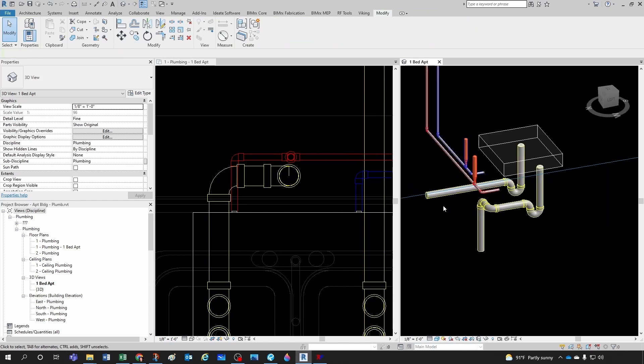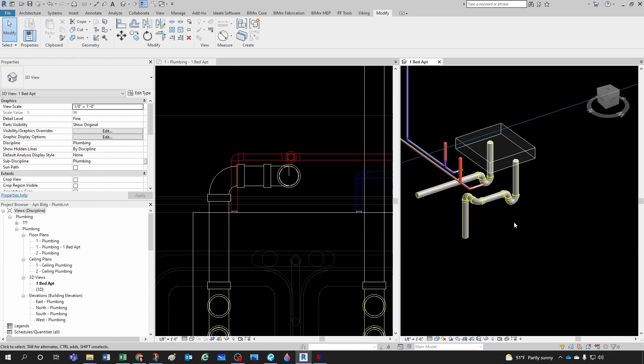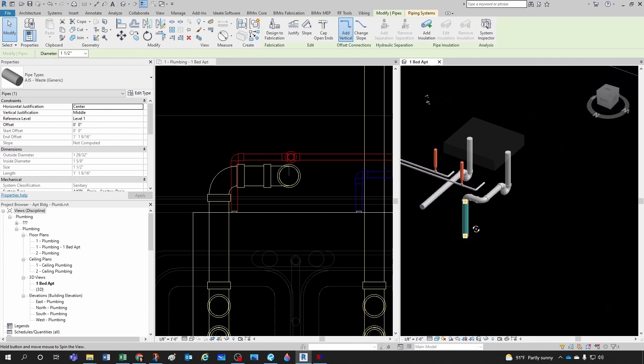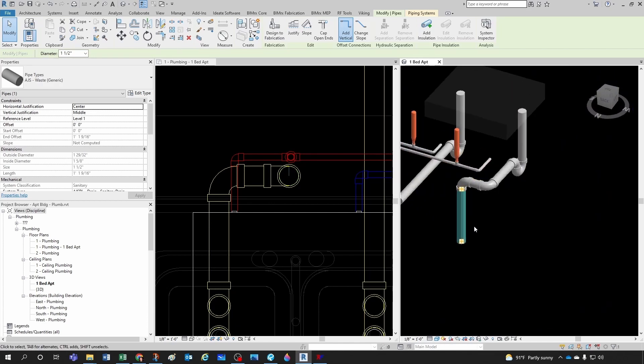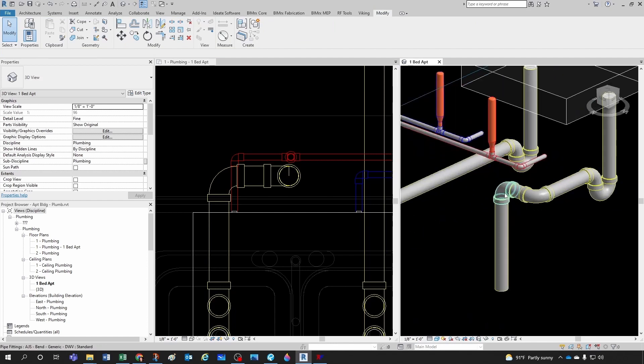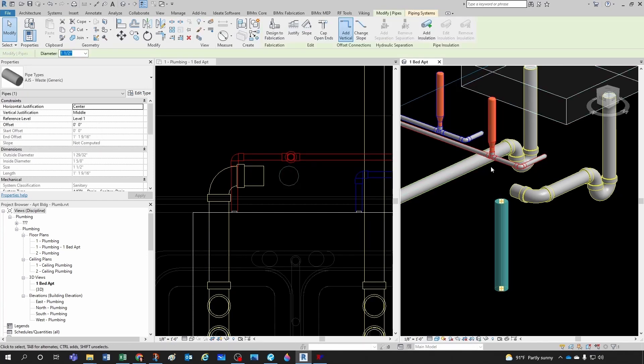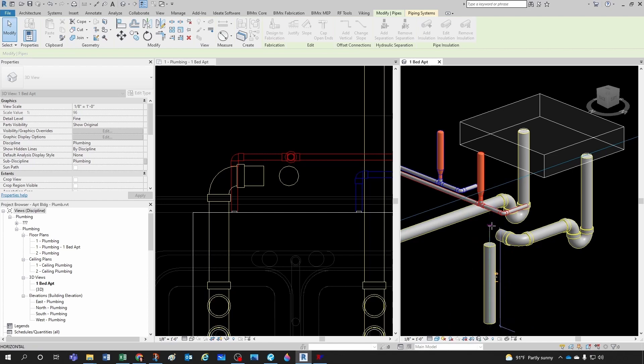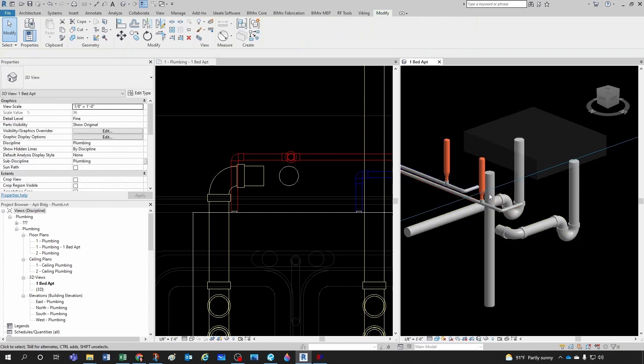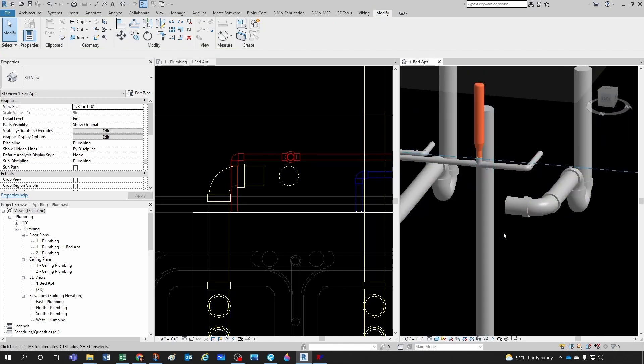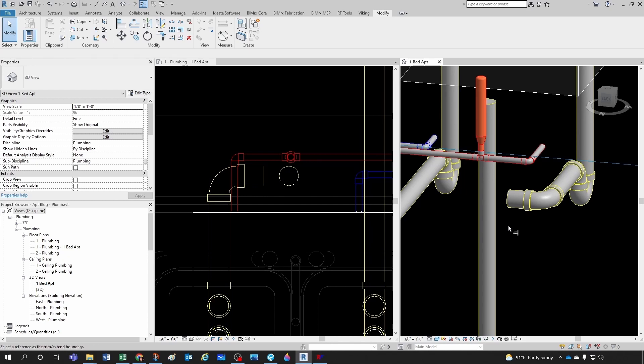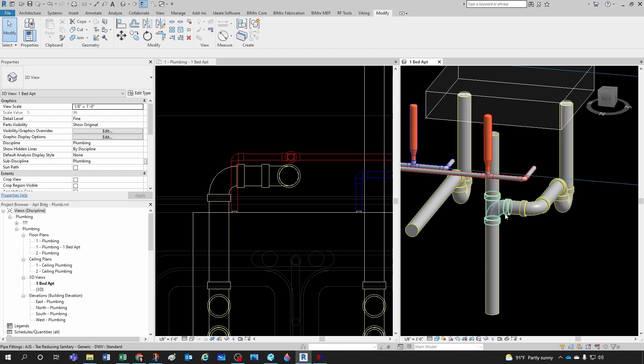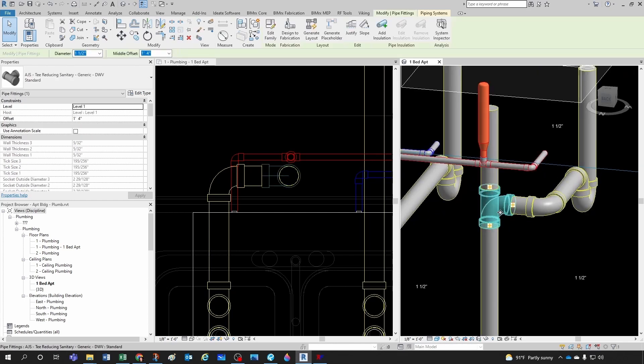A tip for orbiting: if you don't click on anything, orbiting can be a little anarchic. But if you click on an object first and then orbit, you center the orbit around that selected object — that can be really helpful. I'm going to delete the elbow and extend the pipe upward. To keep it perfectly vertical, hold Shift while stretching. Another trick: use the Trim/Extend command — I have the shortcut set to TE. Click the pipe you want to extend to, then the pipe you want to extend, and it introduces a sanitary tee based on your routing preferences.